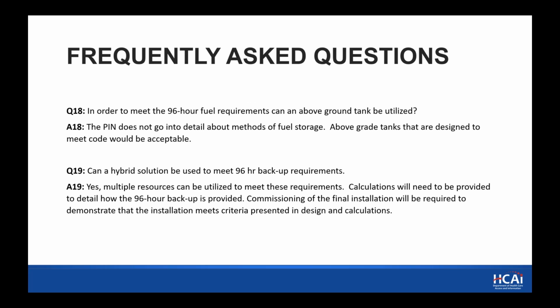Number 18: in order to meet the 96-hour fuel requirements, can an above grade tank be utilized? The answer: the PIN doesn't go into detail about methods of fuel storage. Above grade tanks that are designed to meet code would be acceptable. 19: can a hybrid solution be used to meet 96-hour backup requirements? The answer, yes. Multiple resources can be utilized to meet these requirements. Calculations will need to be provided to detail how the 96-hour backup is met. Commissioning of the final stage installation will be required to demonstrate that the installation meets criteria presented in design and calculations. So yes, a hybrid solution is acceptable.